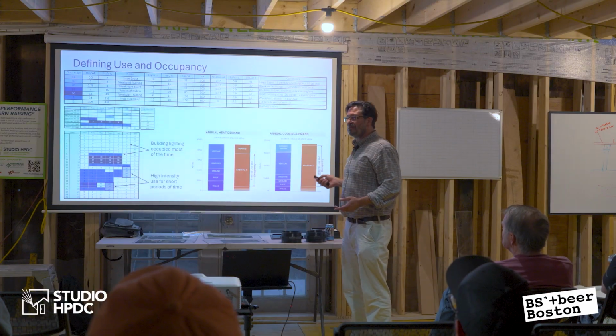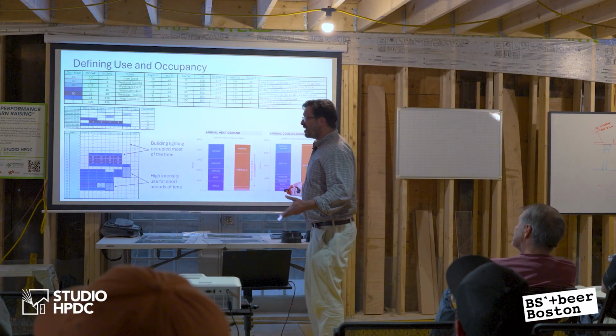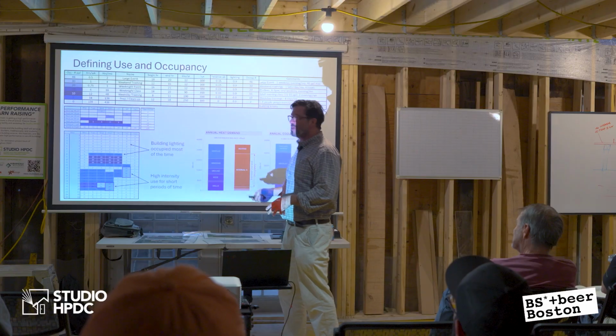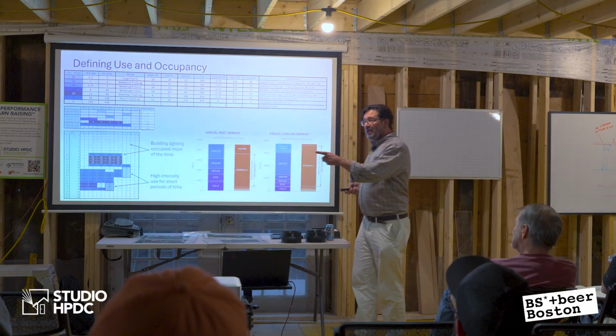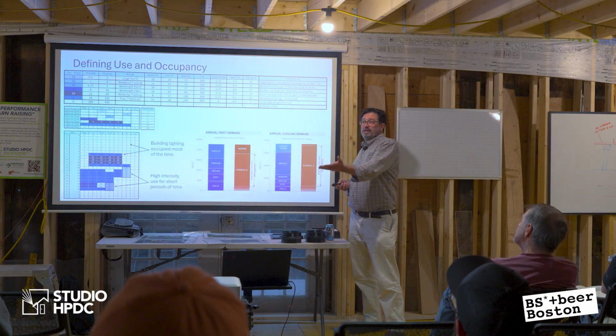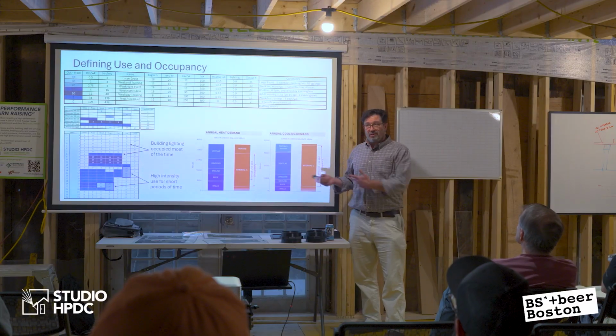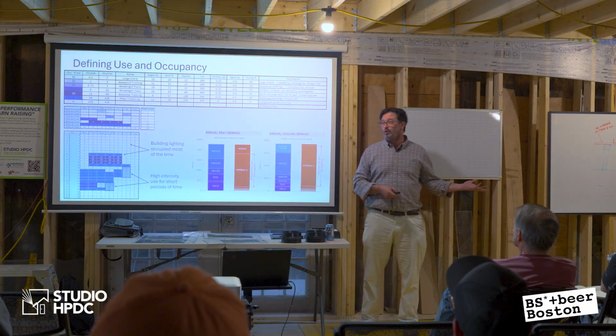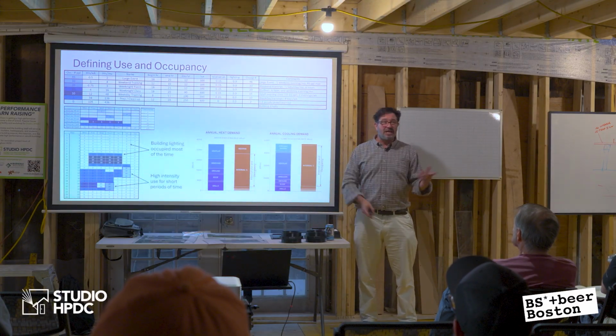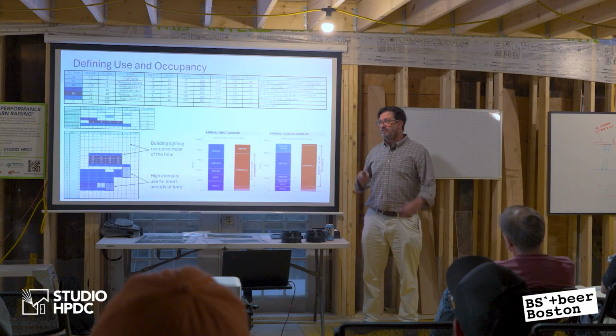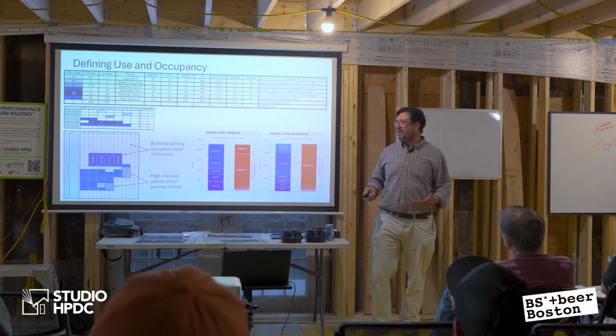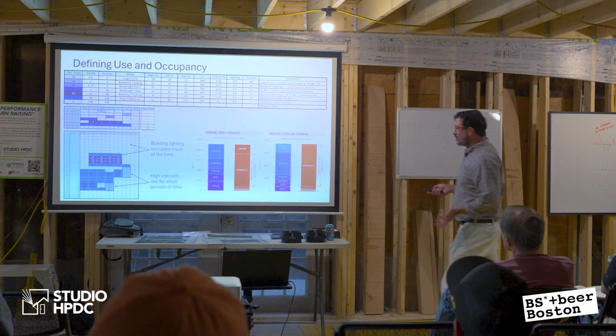And Amy, thanks for sitting with Andy and going through all this stuff and saying, okay, on this day we're going to have this many people and then it'll spike. Now, this is really important because Ross mentioned ventilation. Well, you've got 50 people in a space, that's a different animal from 2. But they're in the same building and the hours are swinging wildly in terms of the loads in the building for ventilation and the internal heat gains. So that's kind of cool.